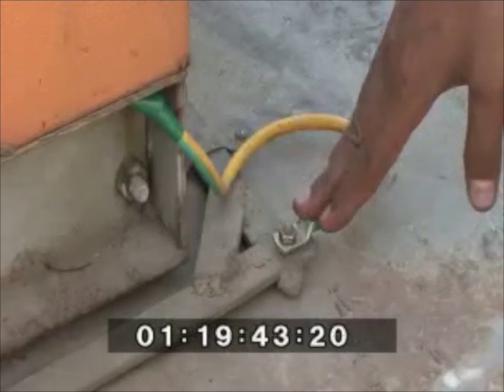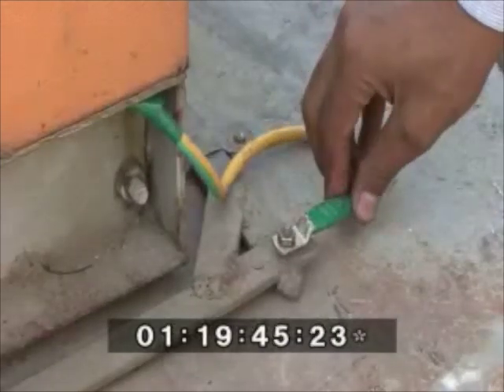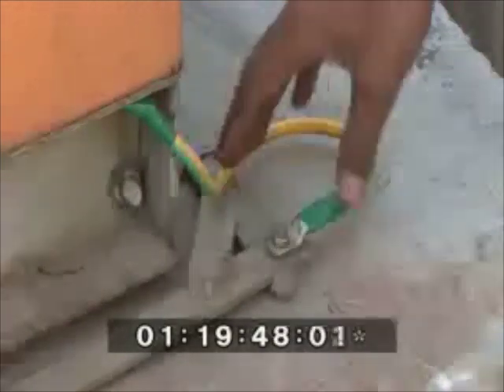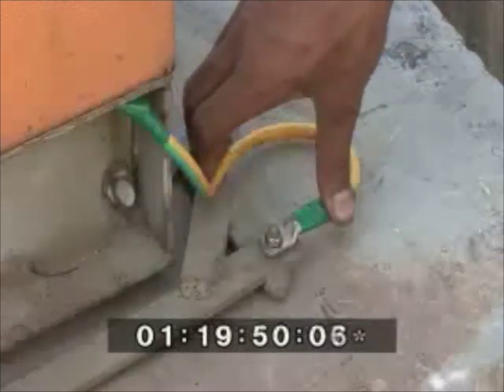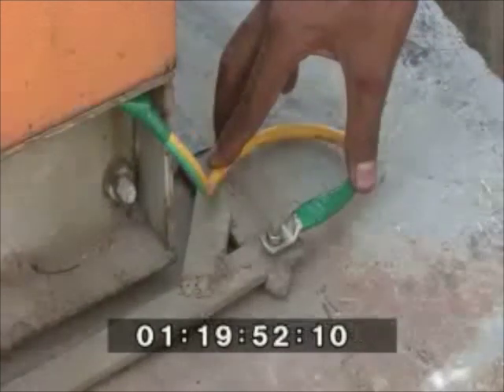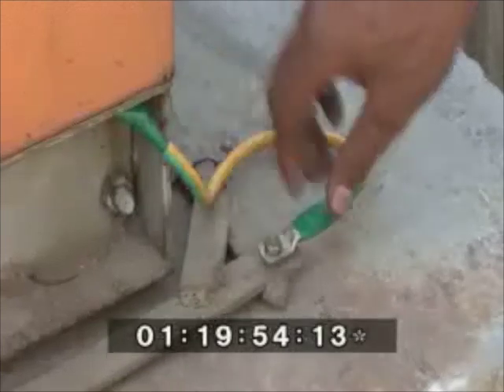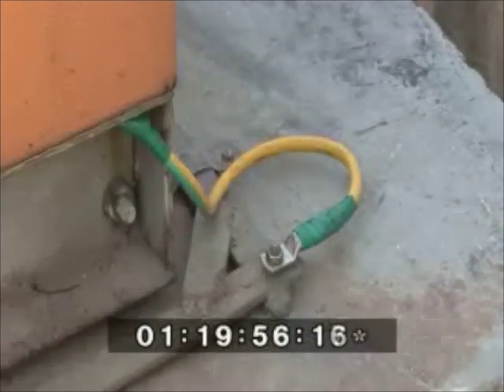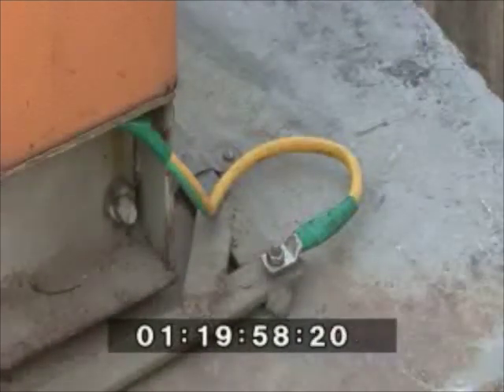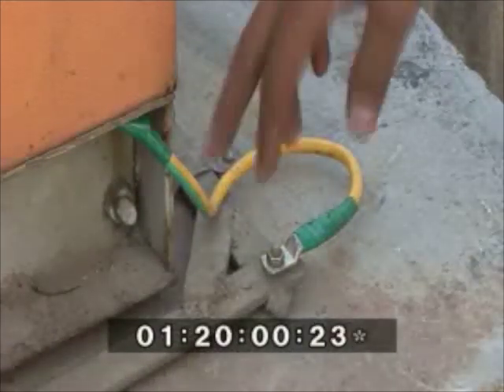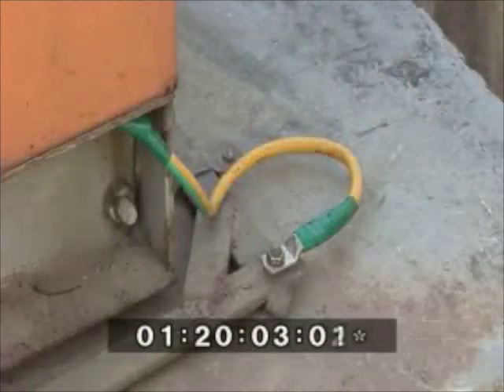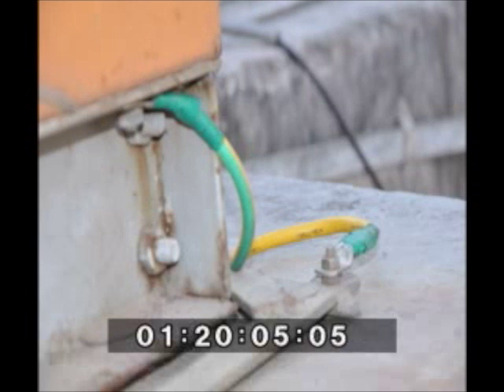You can see the DG earthings. The earthing strip is connected to the canopy by the GI cables. In case of lightning or any other high voltage falling on the canopy, the same will be absorbed by the earthing system. This is for the safety of all the equipments housed in the canopy.